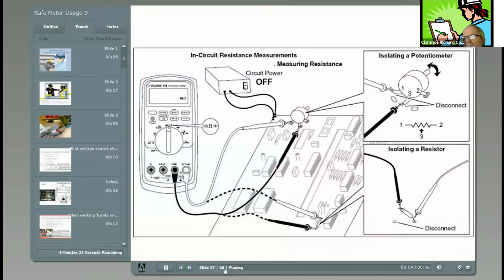Caution: to avoid possible damage to the meter or to the equipment under test, disconnect circuit power and discharge all high voltage capacitors before measuring resistance. The meter measures resistance by sending a small current through the circuit. Because this current flows through all possible paths between the probes, the resistance reading represents the total resistance of all paths between the probes.